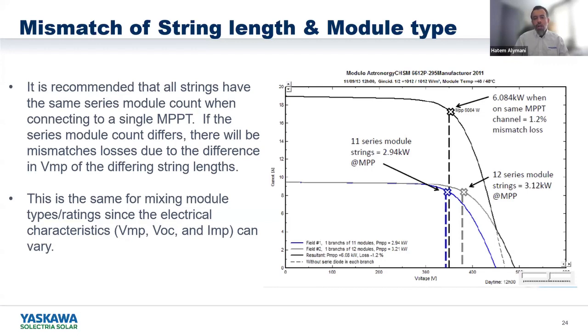Because as you see here, each MPPT can theoretically be treated as a separate inverter. So for each MPPT, all the strings in the MPPT have to have the same length, the same number of modules, the same module type in terms of wattage and brand, so we can make sure that there is no mismatch there.